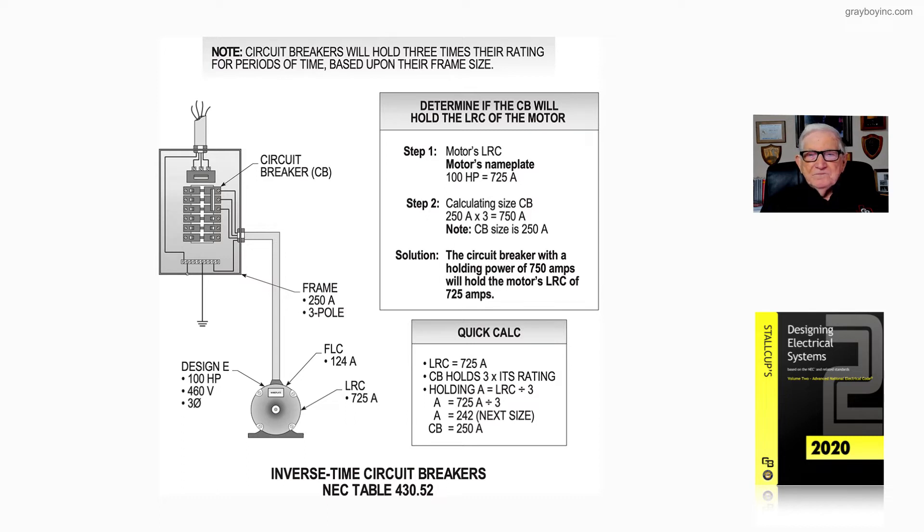If we take a circuit breaker at 250 amp rating times three, that's 750, which is greater than the 725 amps in step one. So if the motor doesn't take a long period of time to accelerate its load, that's going to start that motor and its load.